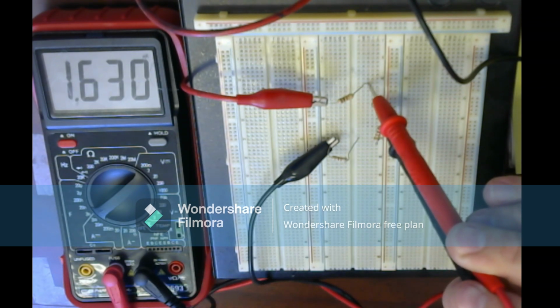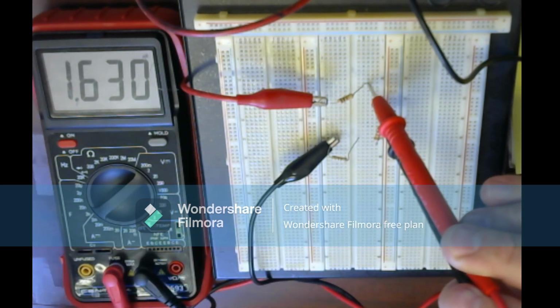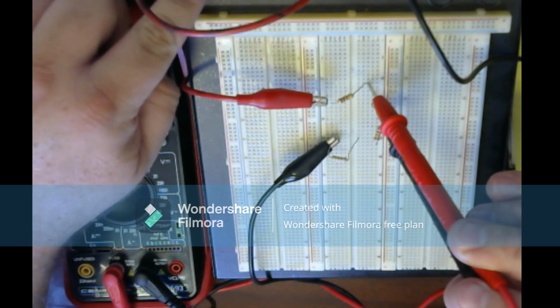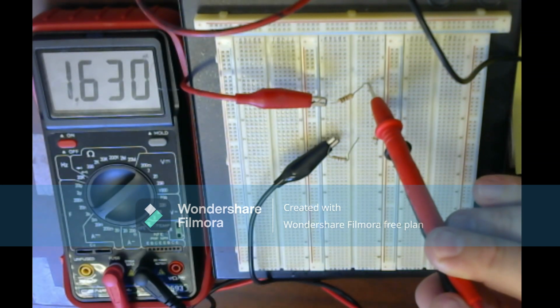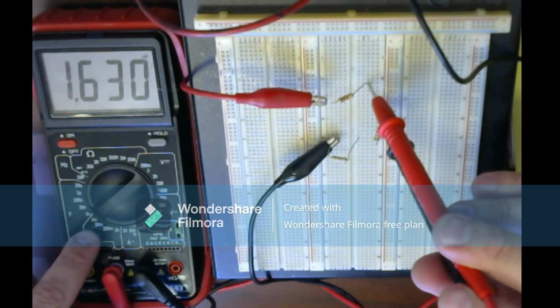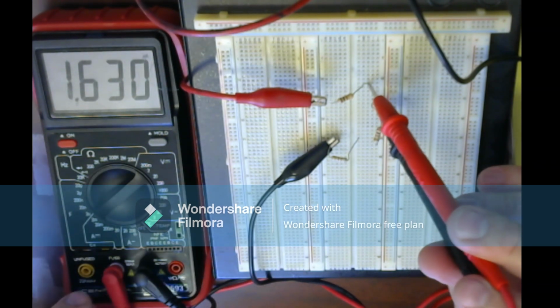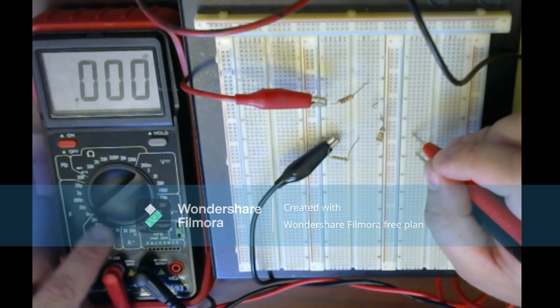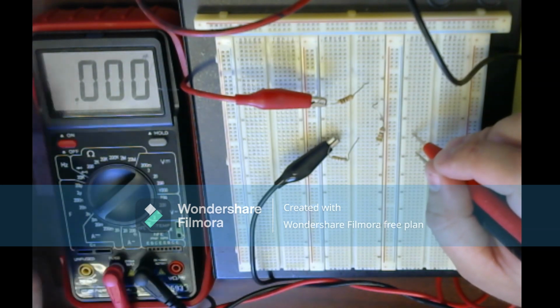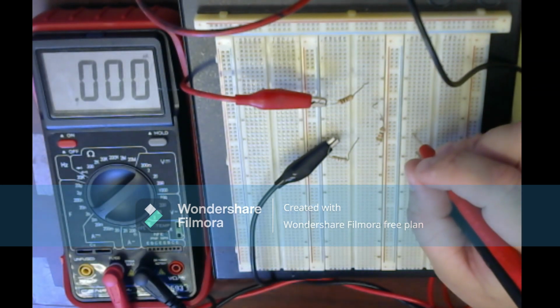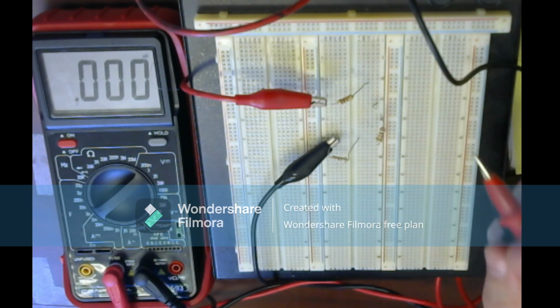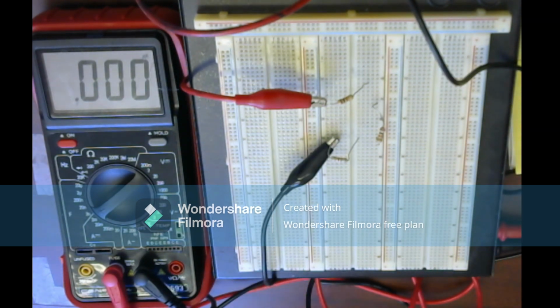Right now, the 200 milliamp fuses are about 50 cents apiece, so the more you blow, the more money you're going to spend. So always remember, turn the power off before you go to make an adjustment with your current, and that includes changing your ranges. Some problems you can have is when you disconnect or change this range, you're actually going to force some of that current up through the meter, which could potentially burn it out. Also, depending on how your circuit is connected, that could be a problem as you're disconnecting or changing the settings on your meter.